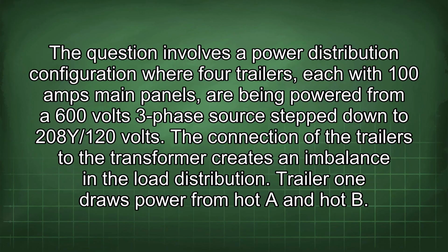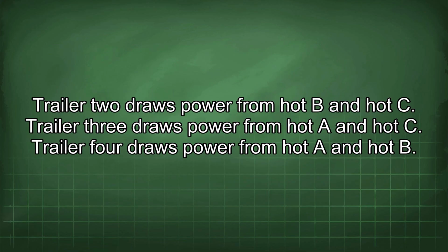The question involves a power distribution configuration where 4 trailers, each with 100 amp main panels, are being powered from a 600 volt 3-phase source stepped down to 208Y/120 volts. The connection of the trailers to the transformer creates an imbalance in the load distribution. Trailer 1 draws power from hot A and hot B. Trailer 2 draws power from hot B and hot C. Trailer 3 draws power from hot A and hot C. Trailer 4 draws power from hot A and hot B.